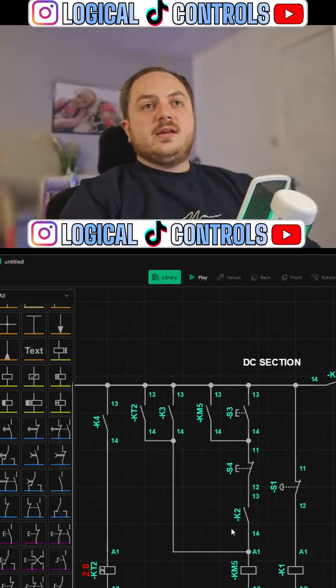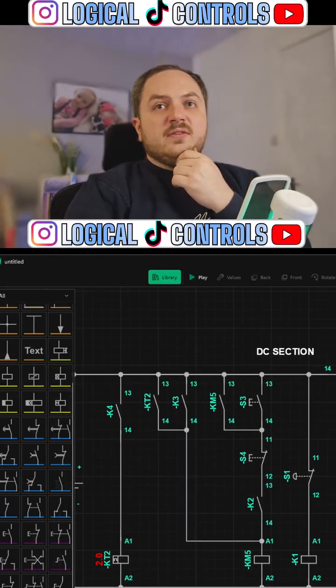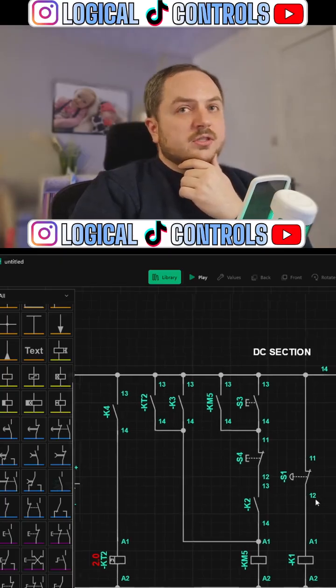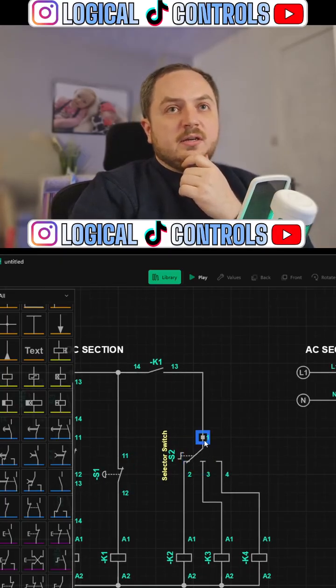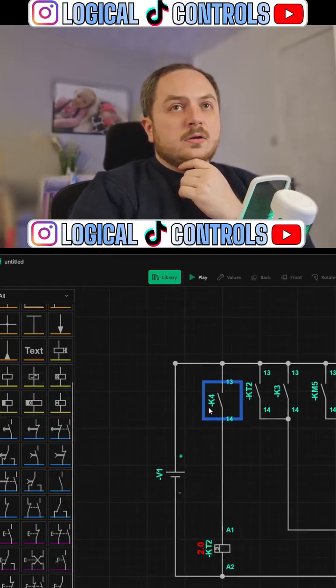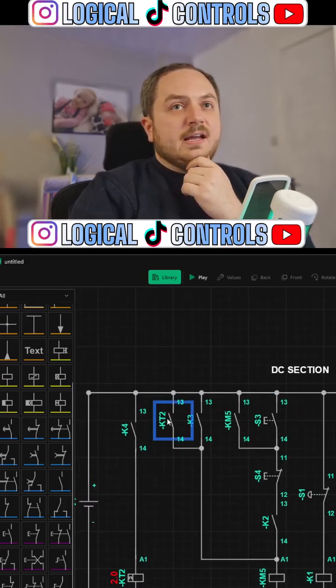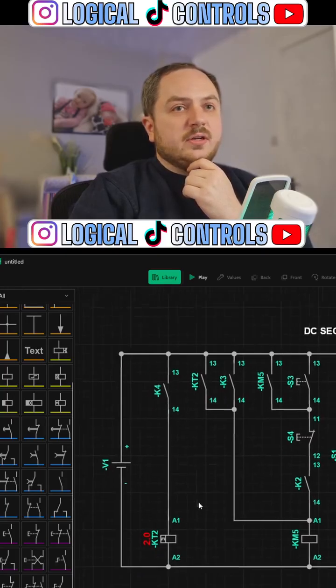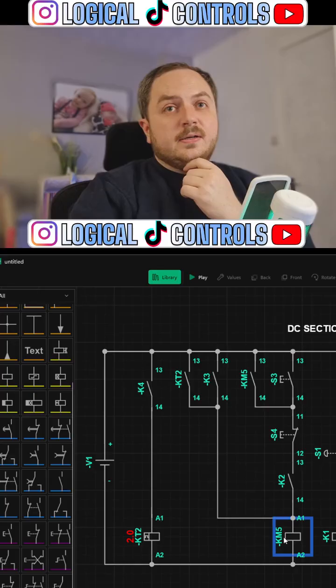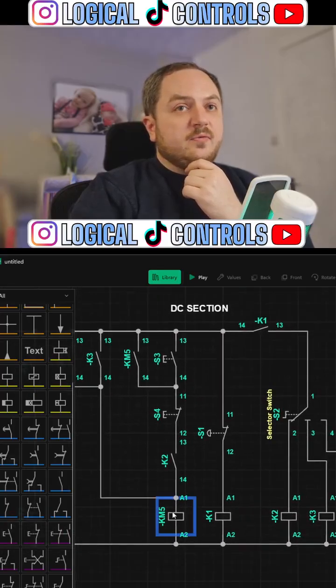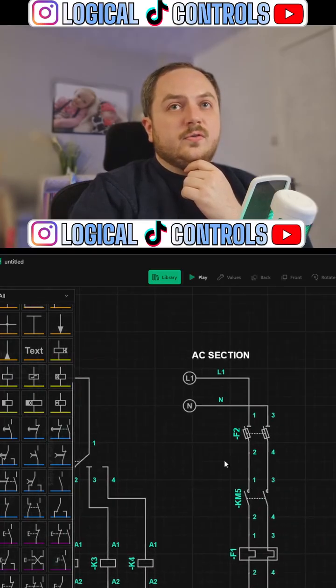So in theory, if I go into the third position on the selector switch, which you can't see there, if I move that switch from 1 to 4, K4 will come on. It'll bring a positive down here onto this flashing timer, and as a result KT2 will start flashing open and closed every, I'm guessing, 2 seconds. That will energize KM5, which is the contactor coil for the motor.